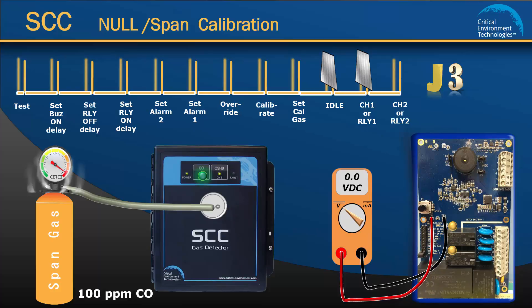Continue the flow of gas and the voltmeter reading will increase. The low alarm LED will come on and relay 1 will be de-energized. As the voltage increases, the high alarm will come on and relay 2 will de-energize. This indicates that the unit has been successfully calibrated and the sensor is responding to gas. Please note, if there are fans connected to the relays, they will be activated at this time and the alarm will sound.